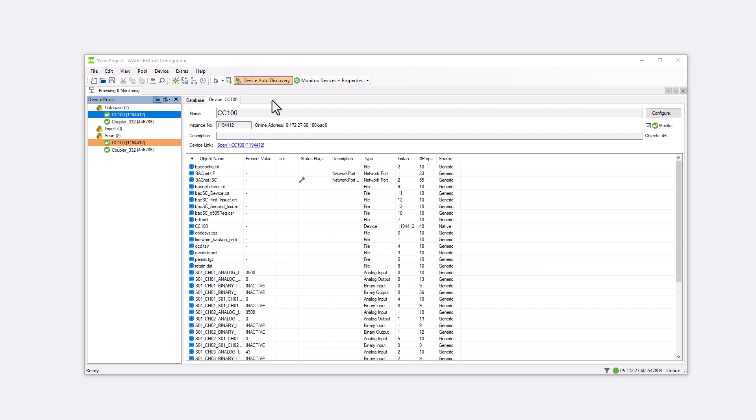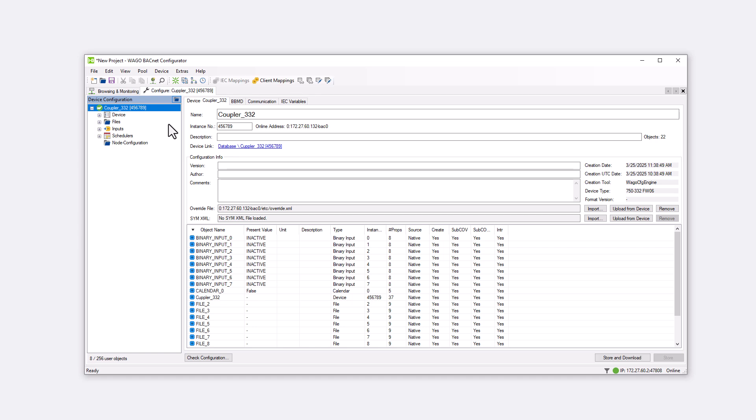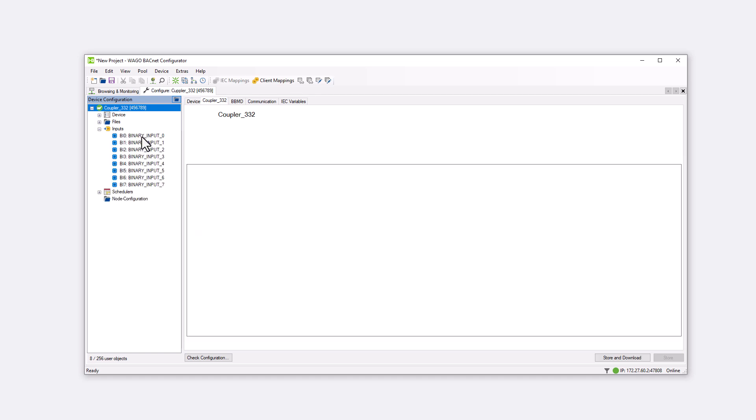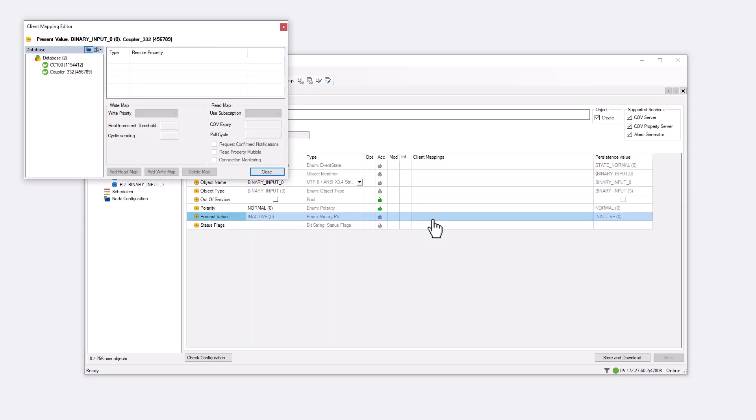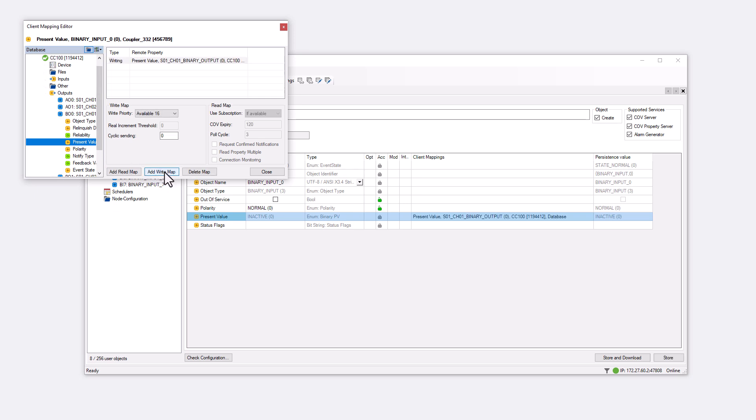Open the Configure tab of the coupler and the Client Mapping Editor in the first binary input. Find the present value of the first digital output on the CC100 and add the mapping with Add Write Map. Here we can select the priority for writing. For real values, the magnitude of the change can be specified and the write operation can be performed cyclically with cyclic sending. Values from 0 to 65,535 seconds can be entered. With 0, writing is not cyclical but only upon value change.